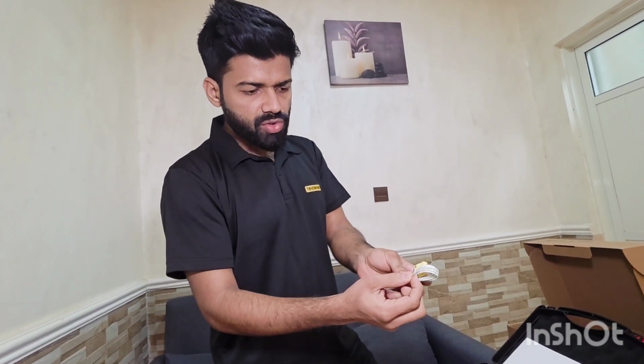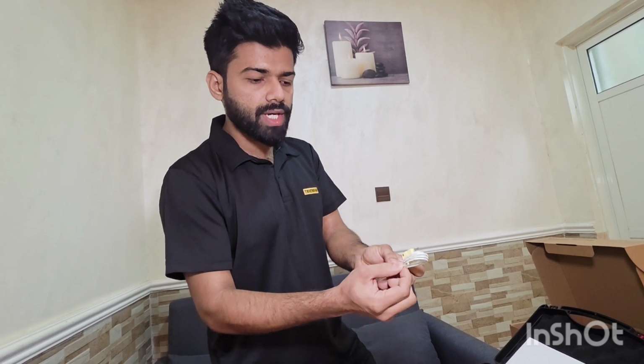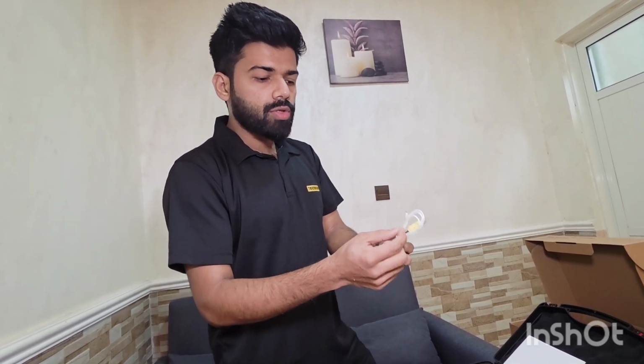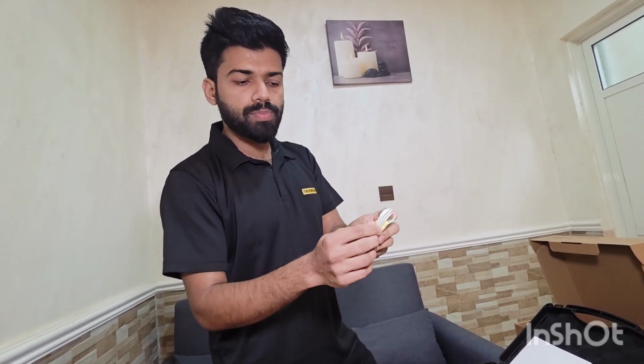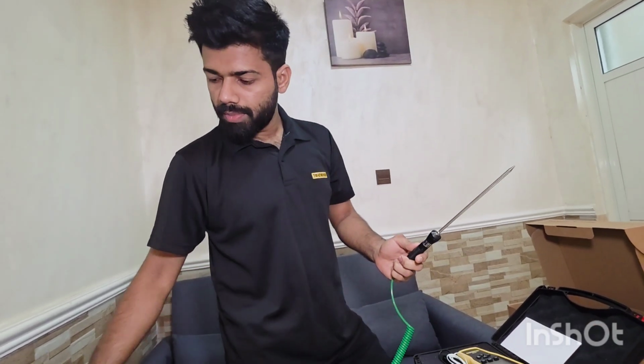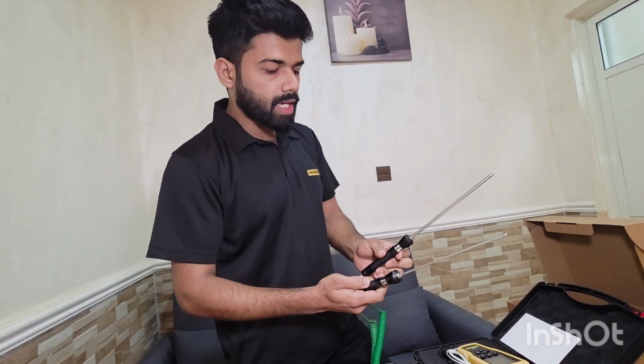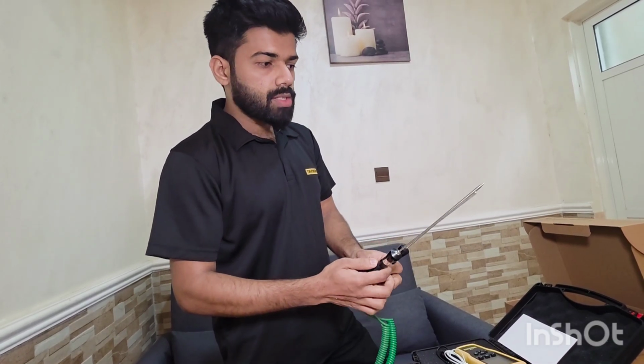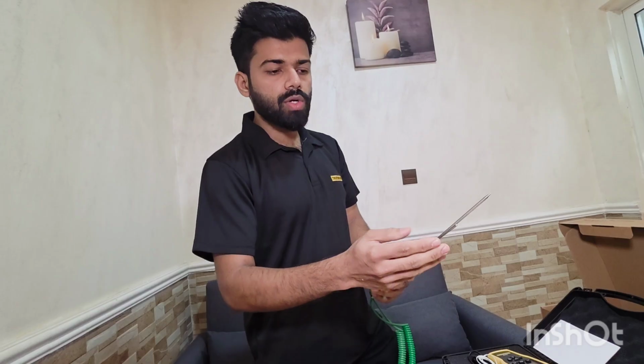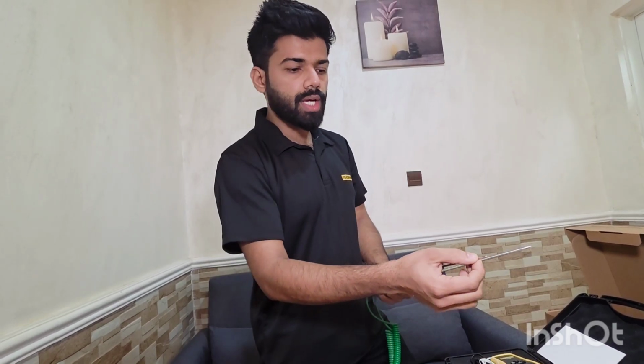So this one is now insulated with this cloth-like structure, so it can measure -50 to 200 degrees Celsius only. Above 200 degrees Celsius, this probe can burn out or change the color of this part. And the TP210 and TP220, the penetration probe and the immersion probe, can measure from -50 to 600 degrees Celsius. So it is tested and safe to use at the factory from -50 to 600 degrees Celsius only. If you go above 600 it can still measure, but at a point it will start melting this part. That's why -50 to 600 degrees is safe to use and recommended by the manufacturer.